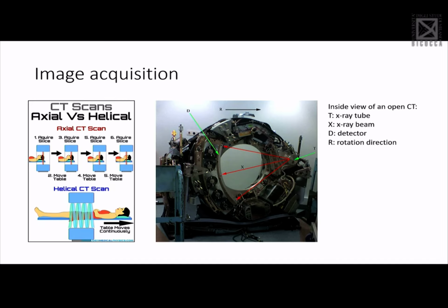You need to keep in mind that in modern days, the X-ray tube of a CT scanner, which might need to dissipate 100 kilowatts of heat, weighs something like 150 kilos, plus all the cooling equipment and the high voltage generator, because we're working with extremely high tension.